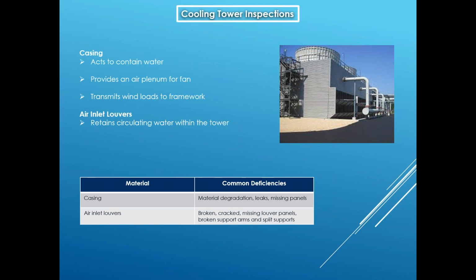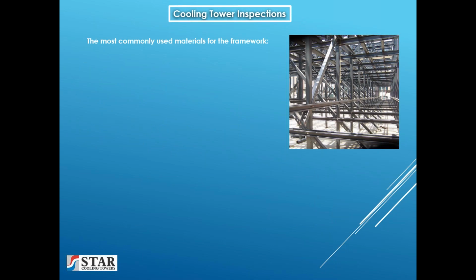The air inlet louvers retain circulating water within the tower and equalize the airflow into the fill. We would look for any holes in the casing that would create air bypass or leakage of the water down the walls or spraying out onto the ground. The louvers and siding panels, to make sure that they're secure, they're properly caulked, and identify any problem areas. The most commonly used materials for the framework is wood, which would be treated Douglas fir or treated redwood, and fiberglass, which would be polyester fiberglass or vinyl ester fiberglass.